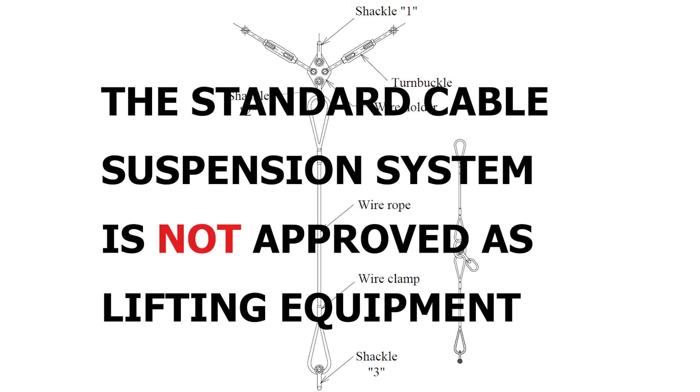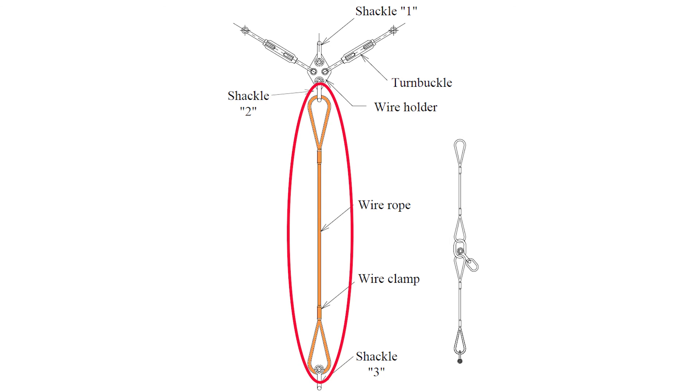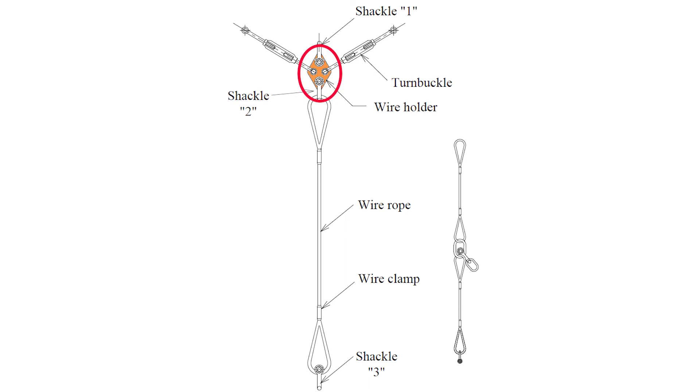The standard cable suspension system is not approved as lifting equipment. If it is needed to use it for lifting the pump and the cables, the wire rope, the shackles, and, if installed, the master links need to be purchased locally with the right certificates and rated for the weight of the pump and the cables. If those components are approved as lifting equipment, they can be used for lifting the pump. Be aware that the wire holder is not approved as lifting equipment, and therefore shackle number one is not allowed to hook onto. Use instead shackle number two or the upper lifting eye in the wire rope.